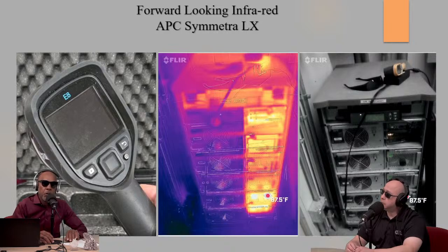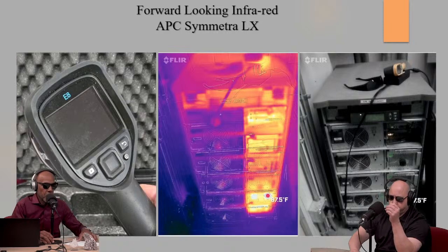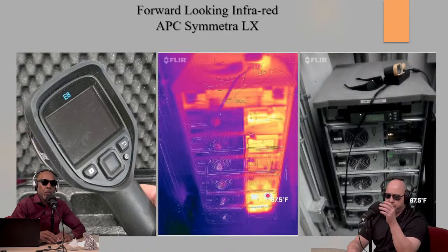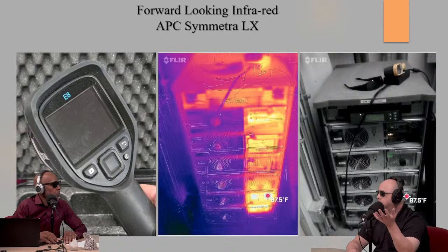What are the benefits of this? It shows you hot spots in your equipment if something is about to fail. On the left side are the power modules themselves within range, but you see those bright or dark orange spots, that's showing battery thermal runaway, where the batteries are overheating. They're going to start to swell, and if they start to swell, they can start to leak, and that causes you to go down because now you have no battery backup.